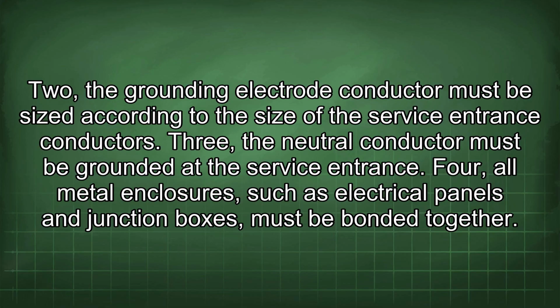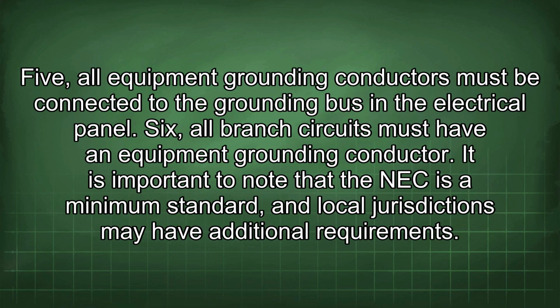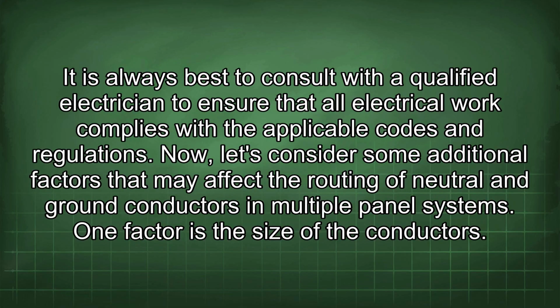4. All metal enclosures, such as electrical panels and junction boxes, must be bonded together. 5. All equipment grounding conductors must be connected to the grounding bus in the electrical panel. 6. All branch circuits must have an equipment grounding conductor. It is important to note that the NEC is a minimum standard and local jurisdictions may have additional requirements. It is always best to consult with a qualified electrician to ensure that all electrical work complies with the applicable codes and regulations.